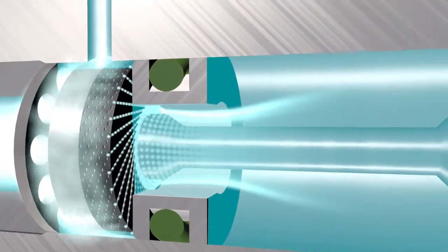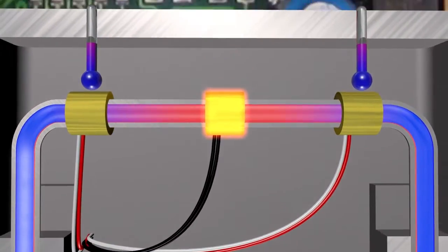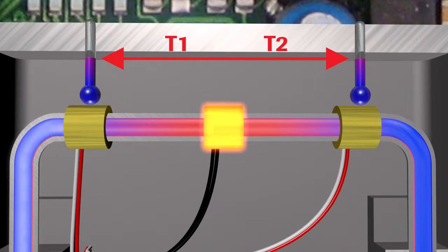The resistance of the laminar flow element also ensures that a small portion of the flow is fed to the sensor. This cold gas cools the first temperature recorder. The second sees the gas that has been heated by the heater.